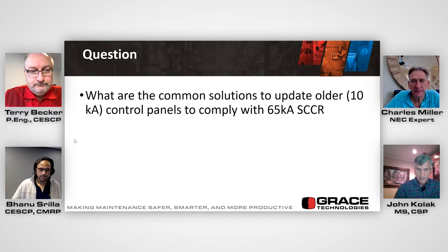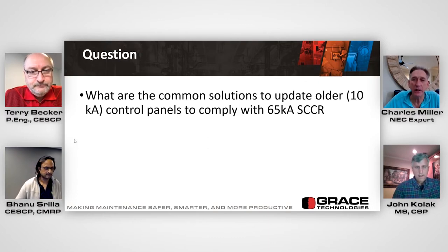Thanks, John. Charlie, do you want to add, please? These requirements have been in the National Electrical Code for a long, long time. A lot of electricians out there say, oh, this is brand new. When did it come in? Like before you were born? They've been out there a long time. For interrupting current, short circuit current, breakers have to have an AIC rating or KAIC rating, and the equipment has to have a short circuit current rating.